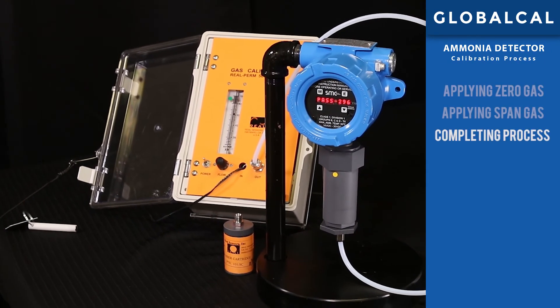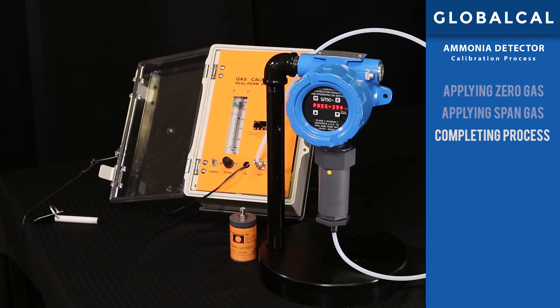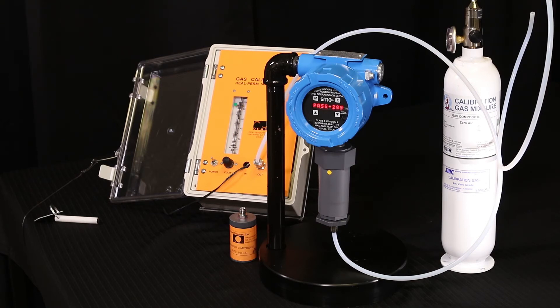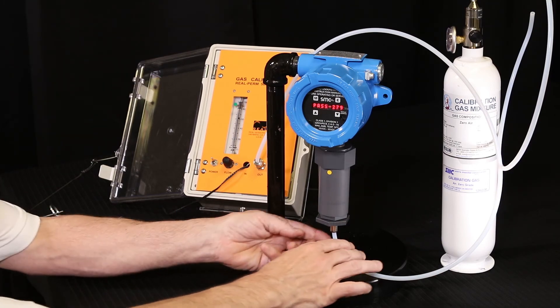Step three: completing the process. Observe the display and you'll notice that the detector will begin a countdown of five minutes and will also display pass. This ensures that the detector will return to normal operation when no span gas is present. As the timer continues to count down, turn off the span gas pump and disconnect the tubing and fitting from the sensor.